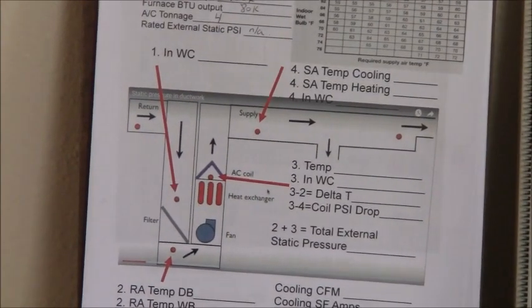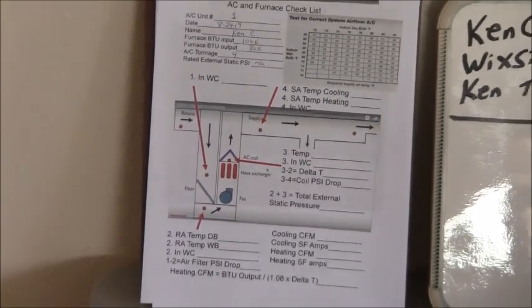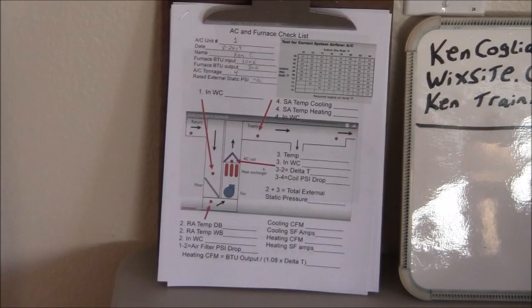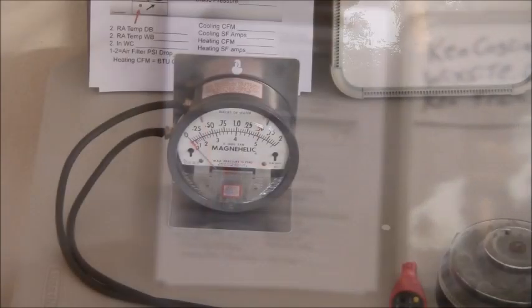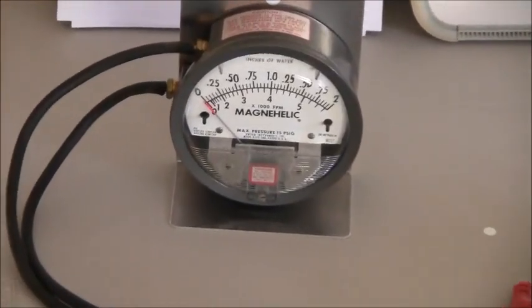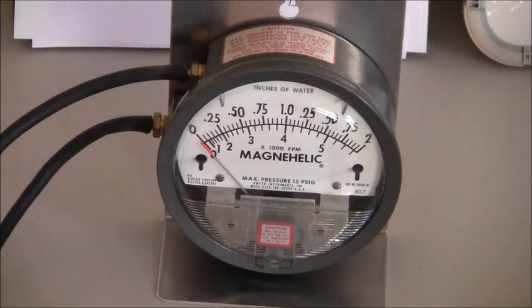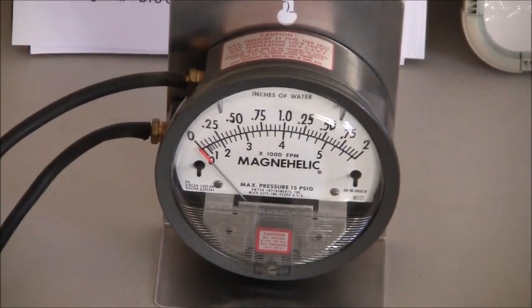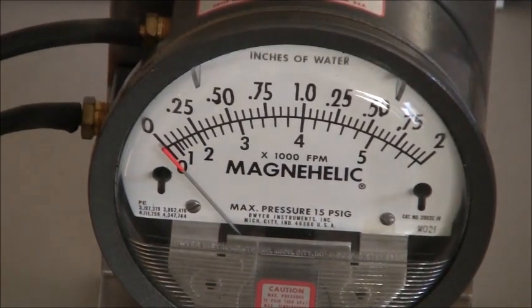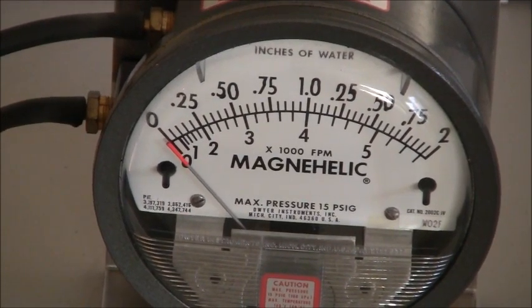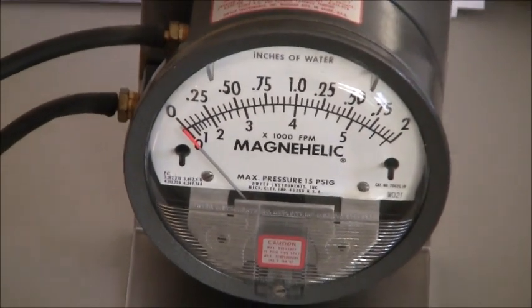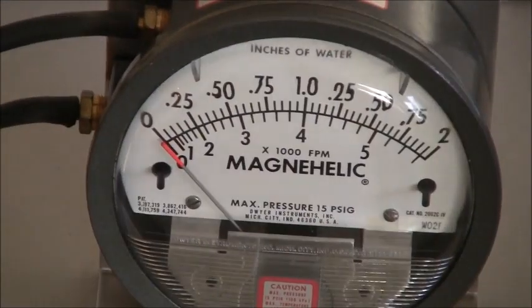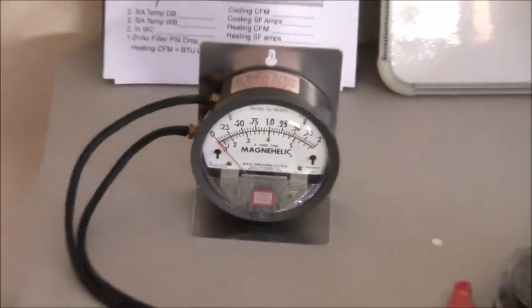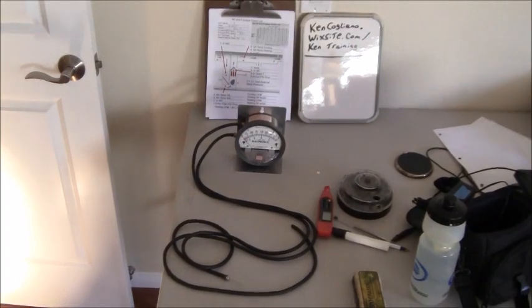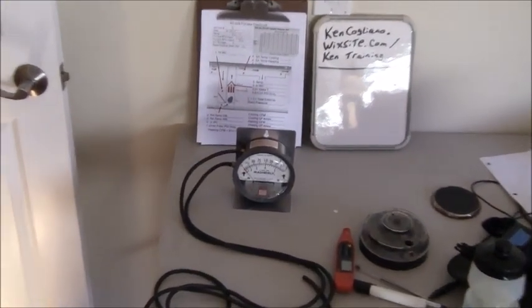We're going to do sample readings with a Magnehelic gauge. This here is a Magnehelic gauge that I have. Luckily I did not have to purchase it, I already had one. This one goes from 0 to 2 inches, but in reality you could just use 0 to 1 inch. If I was going to purchase one, I would not purchase one of these — I'd get one of the new digital ones. This one's 20 years old, so I just happen to have it, and that's why we're using it.